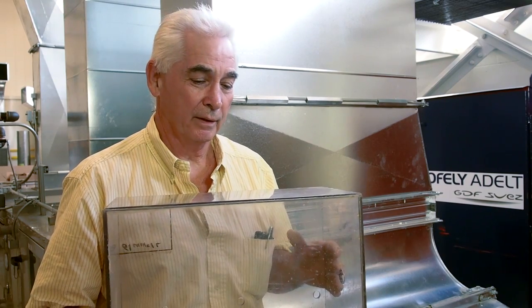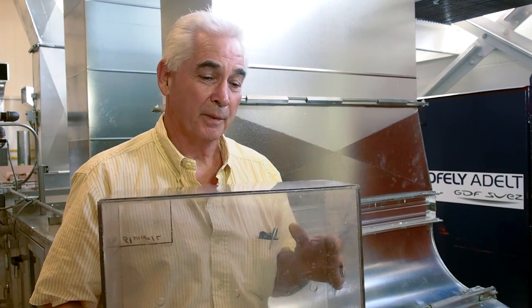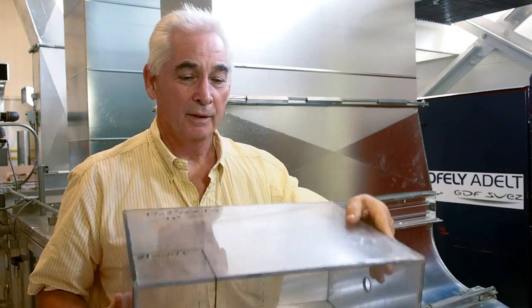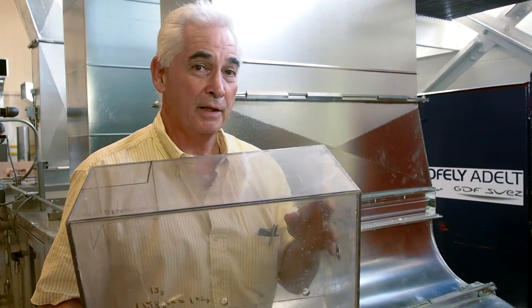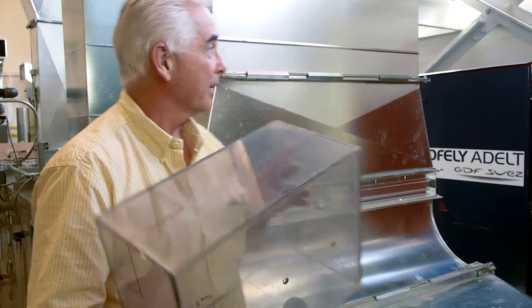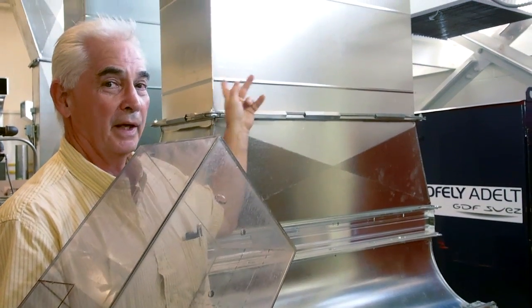This is a demonstration of a duct traverse in a rectangular duct and in a round duct. What we're trying to do is determine cubic feet per minute. We have to determine how many of these cubic feet flow through this piece of duct every minute.